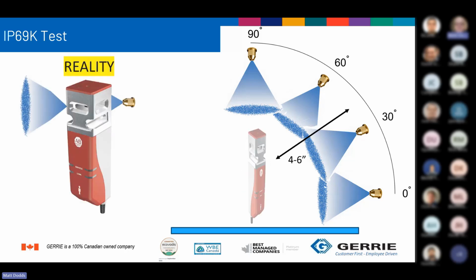However, the reality is that on these machines subject to washdown, the cleaner has that high pressure nozzle and he's trying to strip the paint off this thing, so they're subjecting it to some very high pressures. Depending on the type of switch, water can work its way into the body of the switch. That was what was happening with these other Camlock style switches, it was becoming a bucket. With this switch, because of where the pin is located in the seal, when I blow the water into the switch, it simply blows out the other side because it doesn't have direct access to that seal. So again, they've been up and running. I haven't heard any complaints, and it's been well over a year.